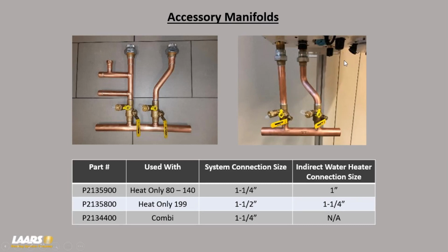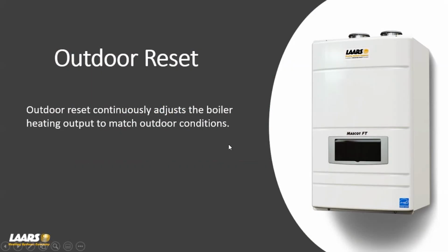There is domestic taps here for your Combi boiler. So this is showing for your hydronic. So the 80,000 to 140,000 BTU input, system connection size is 1.25 inches. So this is all 1.25 inches. Your tappings for your indirect are 1 inch. On the 199 heating only, this primary, secondary is 1.5 inches, and your tappings for an indirect is 1.25 inches. And on the other sizes would be 1.25 inches, and obviously not available with an indirect tapping. So those accessories are available. Next we'll talk about is outdoor reset.